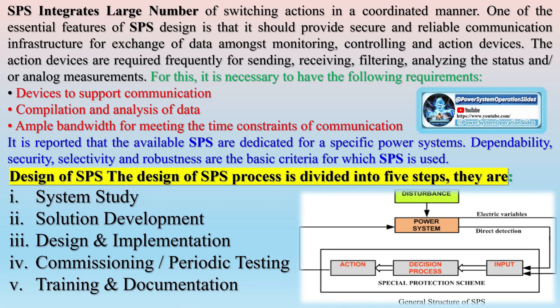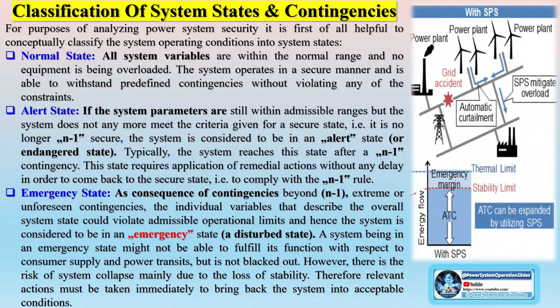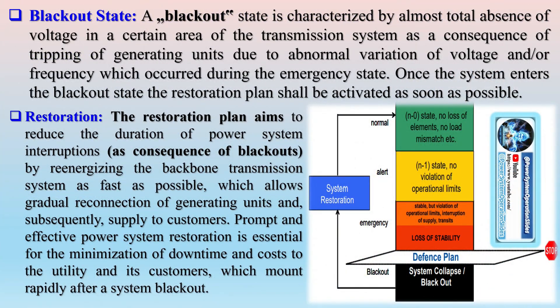In the emergency state, as a consequence of contingencies beyond N-1, extreme or unforeseen contingencies, individual variables describing the overall system state could violate admissible operational limits. A system in an emergency state might not fulfill its function with respect to consumer supply and power transits but is not blacked out; however, there is risk of system collapse mainly due to loss of stability, and relevant actions must be taken immediately. In a blackout state, characterized by almost total absence of voltage in a certain area of the transmission system due to tripping of generating units, the restoration plan shall be activated as soon as possible.